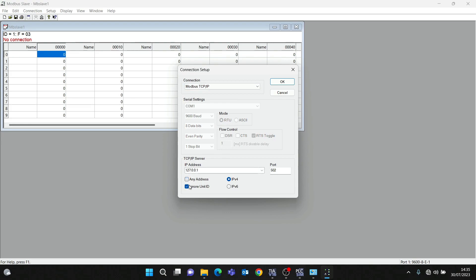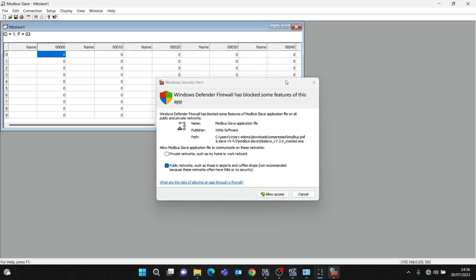I'll do the connection parameters. I'm using TCP, and the IP address is 192.168.0.20. You can see the port is already 502. Modbus default port is 502, but you could use 503 or 504. I'm using the default and this is the IP address of my system which is acting as the server. Press OK.